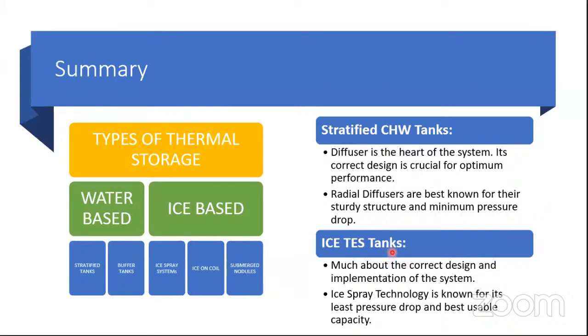And as far as the ice thermal storage tank is concerned, it is much about the correct design and implementation of the system as a whole. And ice spray technology is known for its least pressure drop, because it is an open circuit, and because of the spray mechanism the pressure drop is very less. It is also known for its best usable capacity, very high usable capacity. It can go very close to the sensible. So these are some general findings as far as the study is concerned.